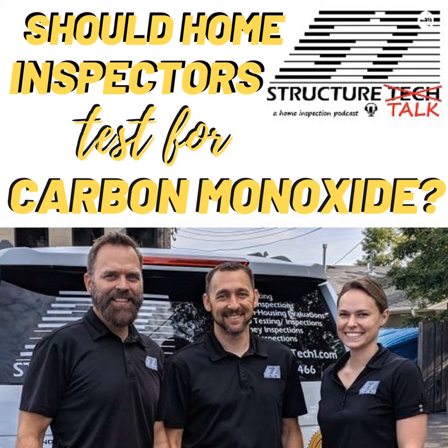The other part is that when the CO is too high, your furnace isn't burning properly, you have a much higher likelihood of soot accumulating on the burners and clogging everything up and making it not operate properly. And number three, it's not going to be operating as efficiently, and it's going to be costing more to heat your house because you're going to have less fuel being used to heat your house and more unburnt gases just going up the flue. Carbon monoxide is the result of that. Right at the finish line, but it's perfect because you put a nice little bow on that. So perfect.